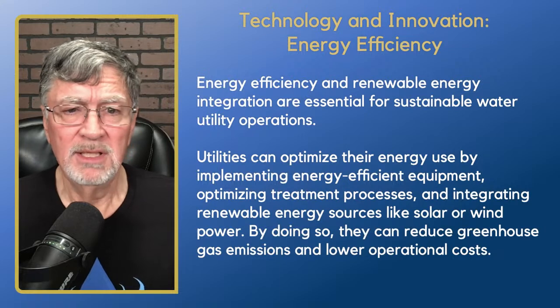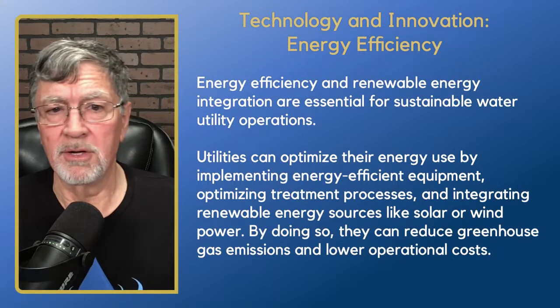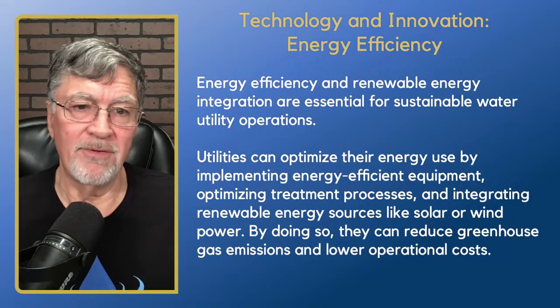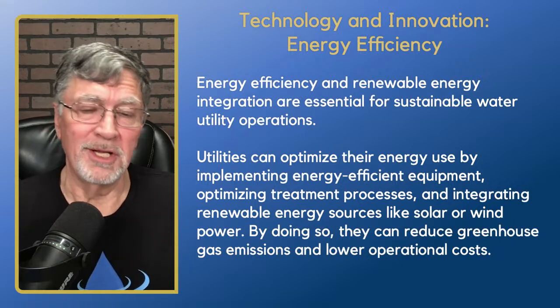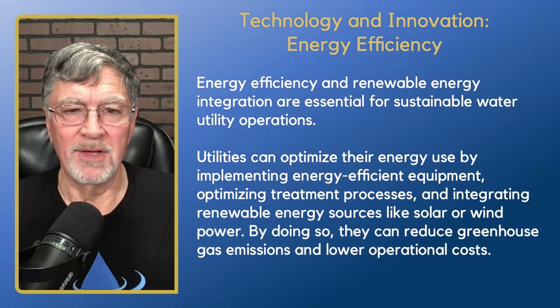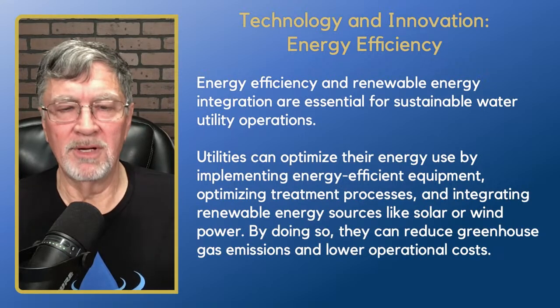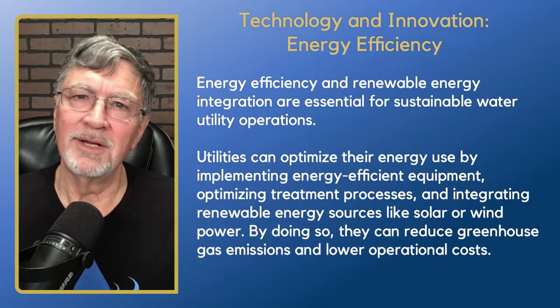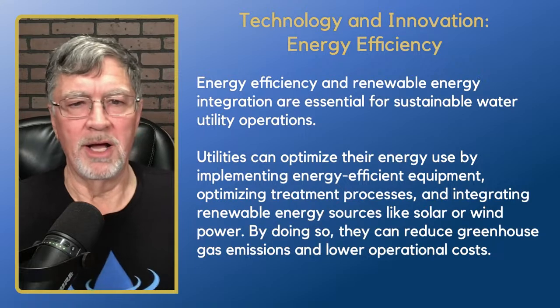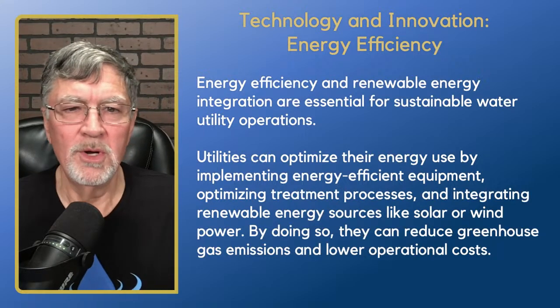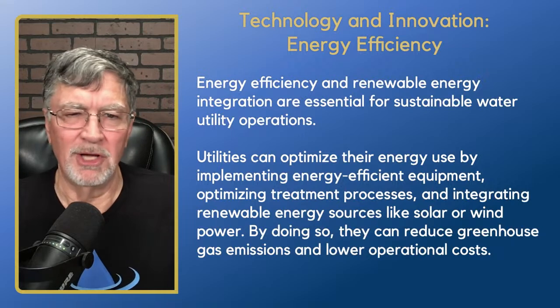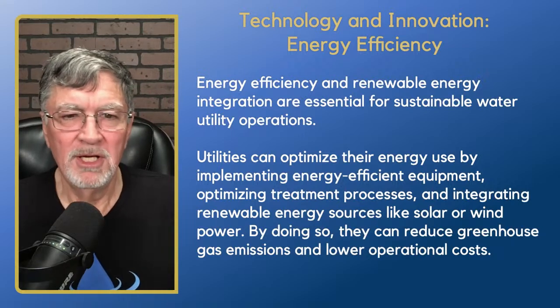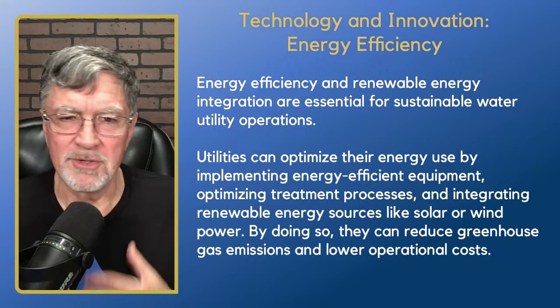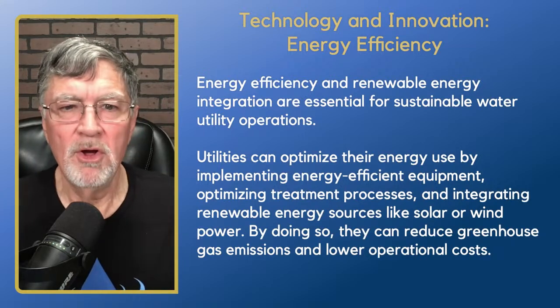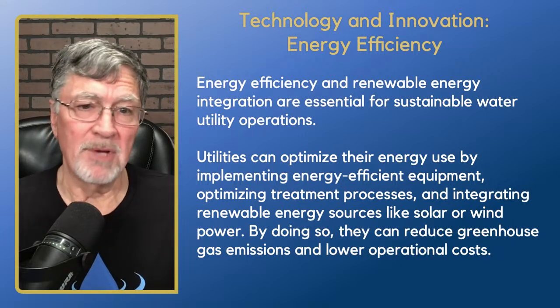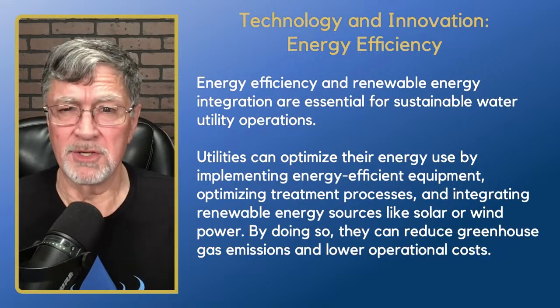A well that's plugged up means you're working that pump harder and using more electricity. As a matter of fact, one of the things we look at to determine when you need to rehab a well is the gallons per kilowatt-hour measurement. You can track that over time and see the loss of efficiency as your well plugs up, because you're pumping more, using more electricity, but producing the same or less water. That means something's going on in your well making it less efficient.